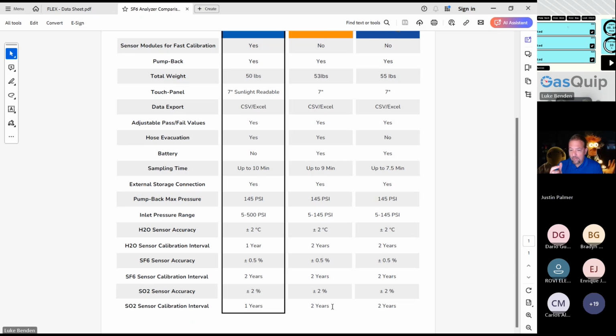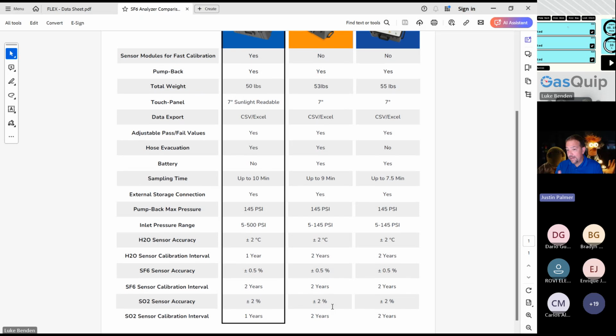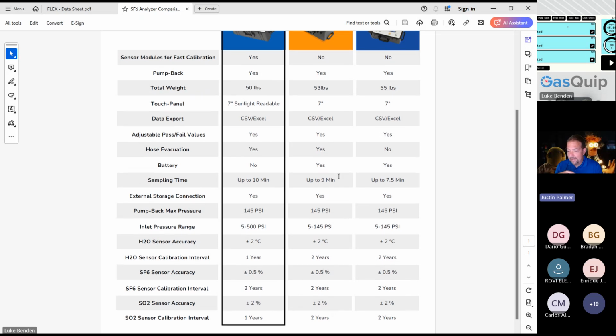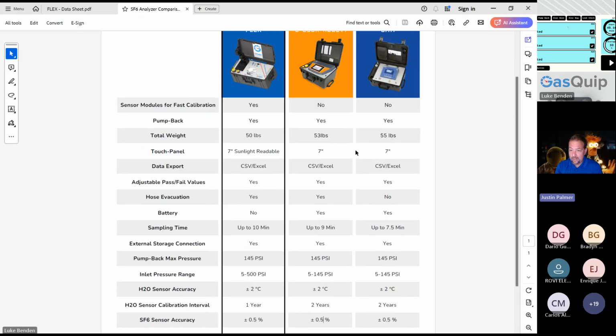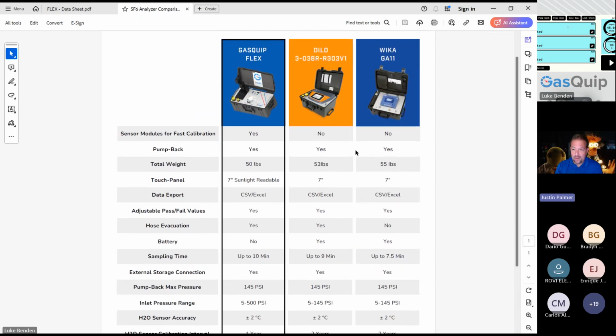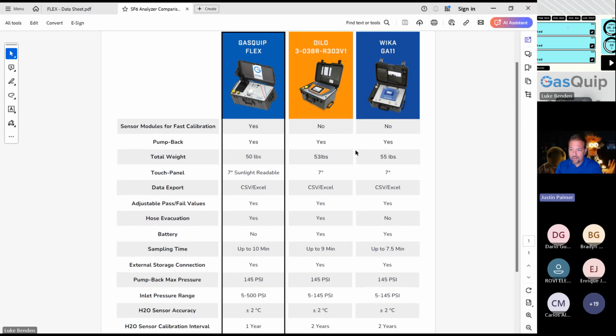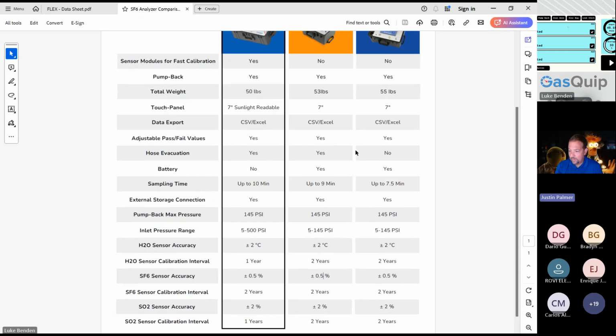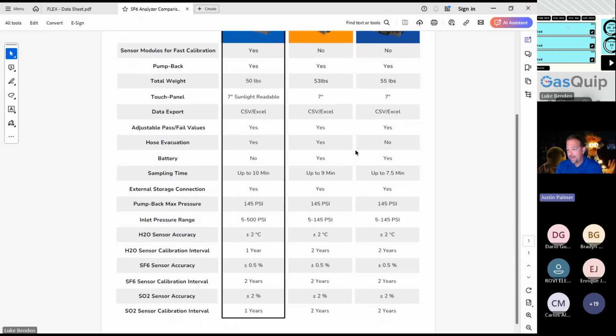But normally our customers are using these for SF6 switchgear or gas circuit breakers, in this case, and they have a limit of 500. So most people go that route because we need to see if it's above the limit or not. Knowing if it's at precisely 35 or 40 parts per million isn't so important. It's below the limit. So most people choose to go with the wider span over the little bit more precision, but you can get higher precision on those if you go to a lower span.